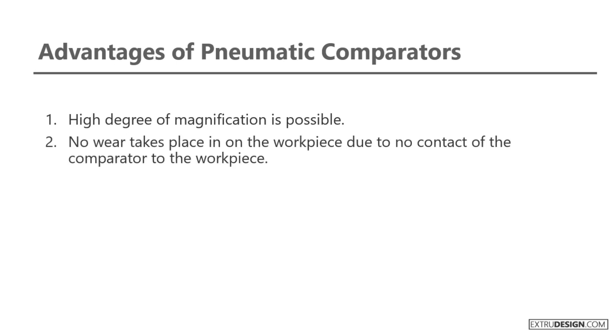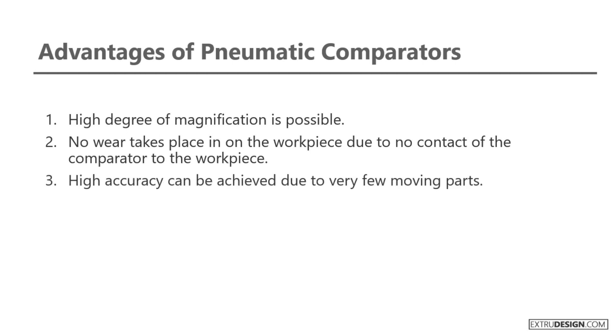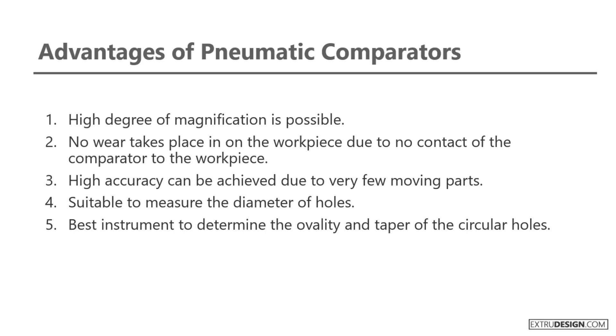Let's see some of the advantages and disadvantages of pneumatic comparators. Advantages: a high degree of magnification is possible; no wear takes place on the workpiece due to no contact between the comparator and the workpiece; high accuracy can be achieved due to very few moving parts; suitable to measure the diameter of holes; and it is the best instrument to determine the ovality and taper of circular holes.